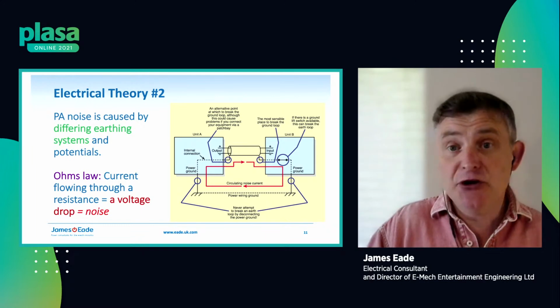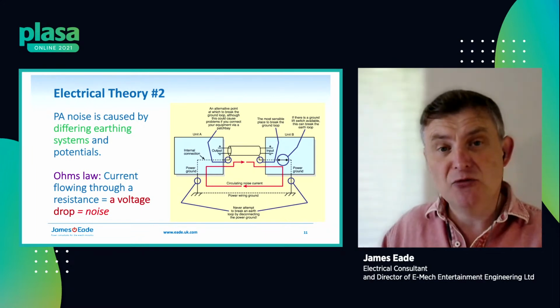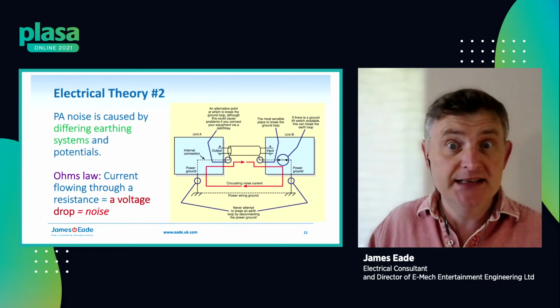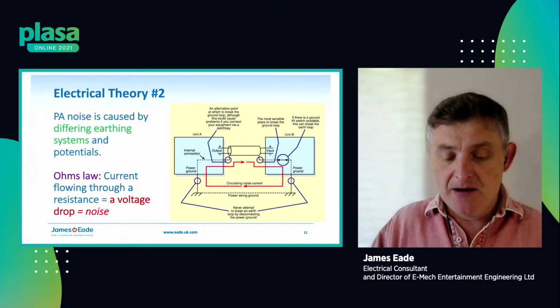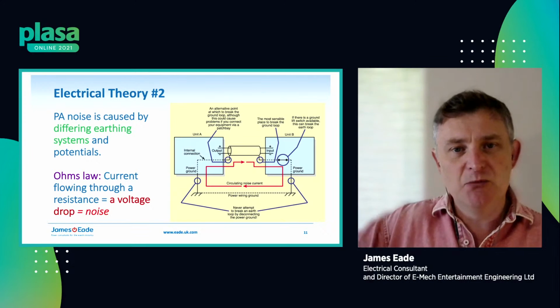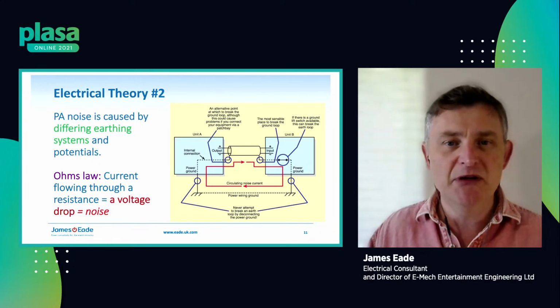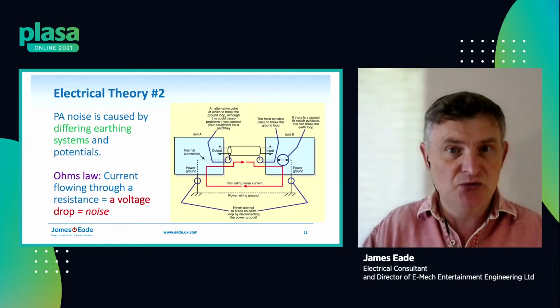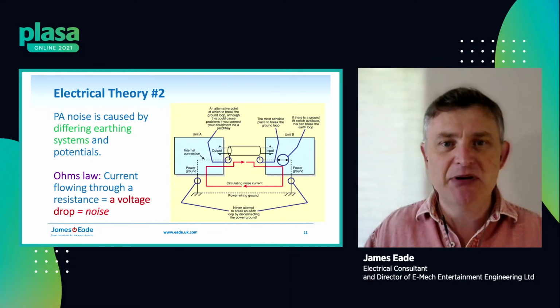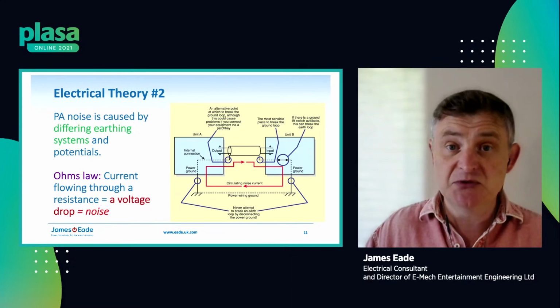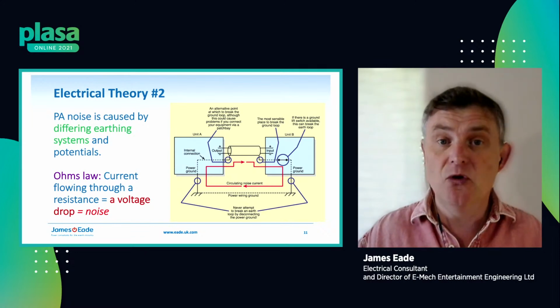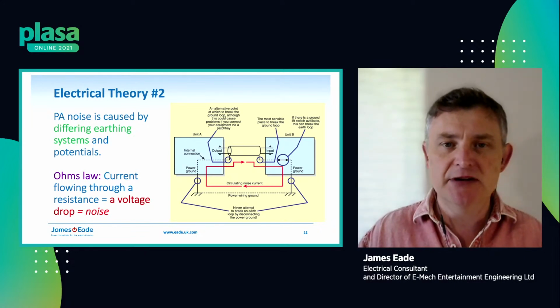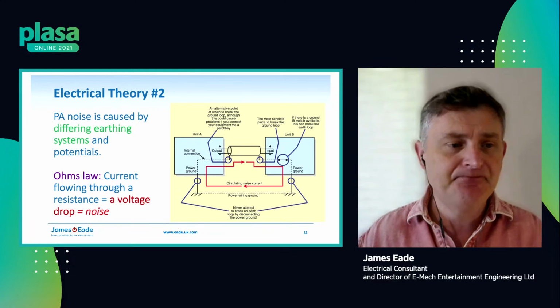Just quickly, if you lose the neutral and you've got all your audio kit on one phase, and neutral failures do happen, the chances are, being the lightest loaded phase, you'll be the one with the largest voltage swing and all your kit will blow up. So it's a very good idea to make sure that in a three-phase system, you balance loads as much as possible, whether it be in a building or on a festival stage running off a generator. The theory is very much the same.